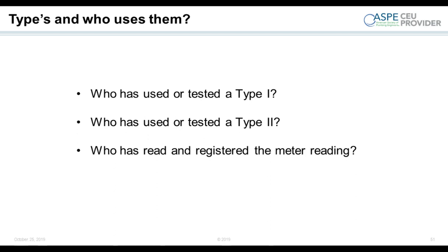But the reason I bring this up is a lot of municipalities require these detector assemblies, and they never read the meter. Reading the meter is very important because it should be important to your AHJ, because often your AHJ is the same company that's making the water. What they're using this meter for is tracking down that non-revenue water.